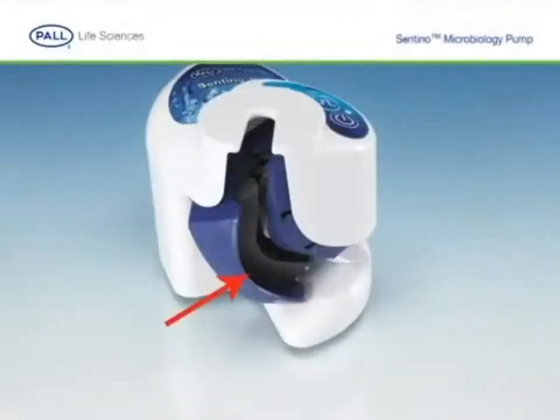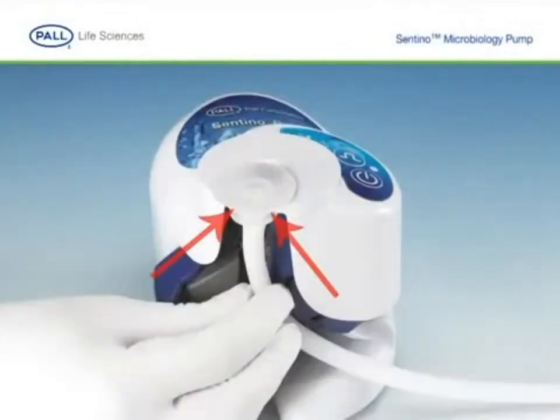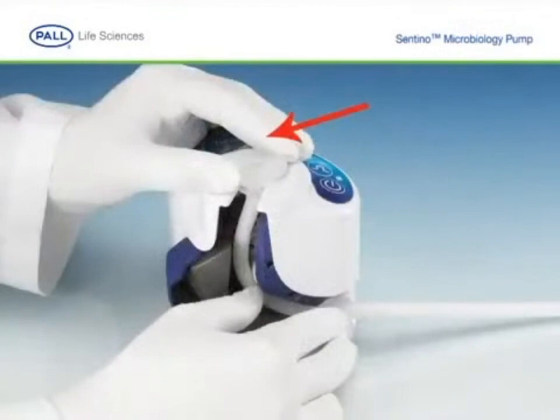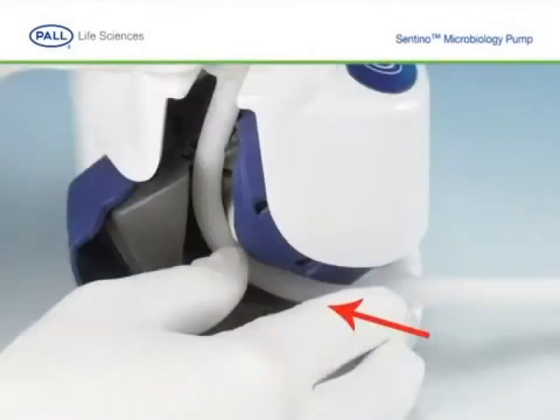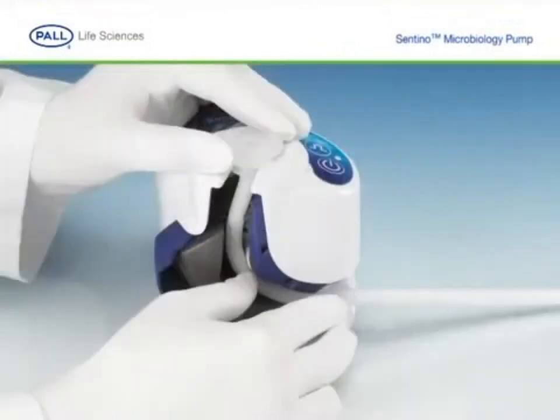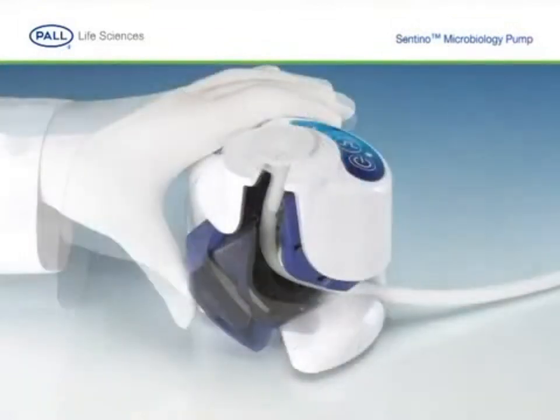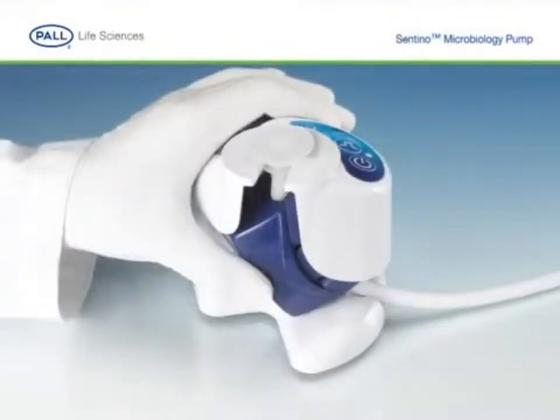Open the pump by pulling on the pump head door. Position the adapter into the guide on the pump housing and slide it until it is firmly seated. Position the tubing into the guide slot on the base and tuck the tubing into the slot on the pump head. Remove tubing slack by gently pulling the tubing against the rollers as you close the pump loading door.